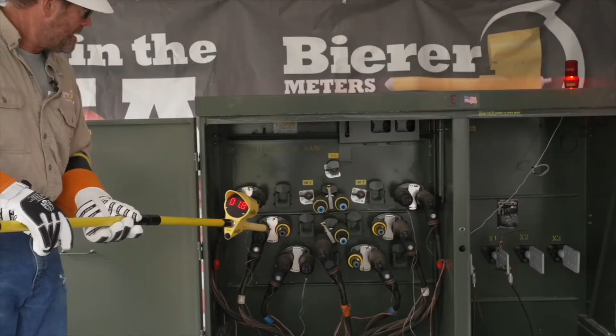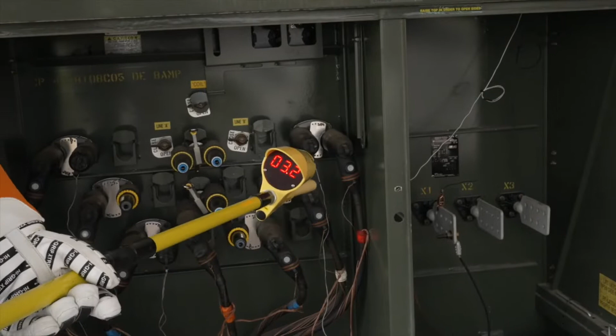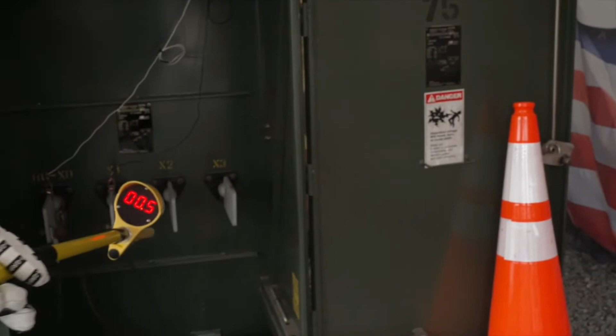You all see those numbers coming up on this overhead line, so we know at least one of those phases is energized. Let's say you have capacitive test points with dust covers on them - you can simply go to the base of your elbow and it'll pick up that semicon material just to verify if it's energized. Or maybe you don't have capacitive test points, you have secondaries - you can approach secondaries as well. You guys get that?